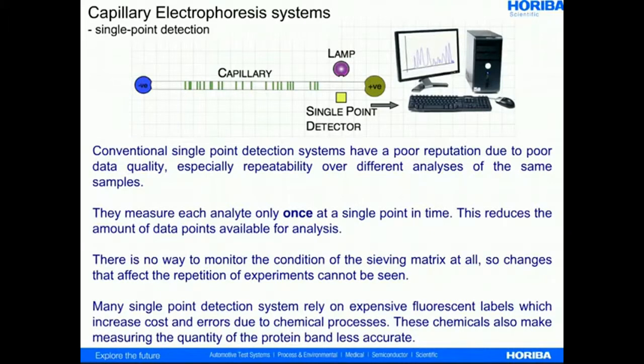It also means that all you're doing is monitoring the movement of the analyte across that small window, with no way to monitor the condition of the sieving matrices in your capillary — so changes that affect repeatability or the repetition of experiments cannot be seen. Additionally, the majority of good data from single point detection relies on expensive fluorescent labels, and sample preparation time can be three to four hours, whereas sample preparation on a multiple point detector is done in about 10 minutes.